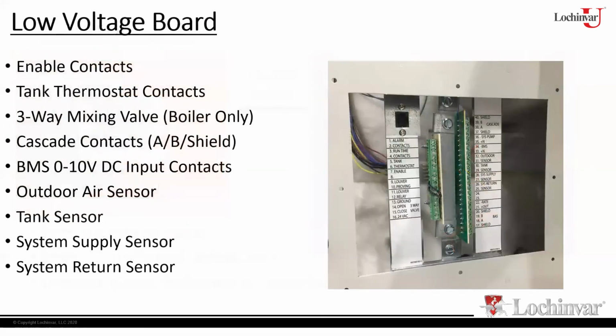Now on the back side of the heater will be our interface for your external items. This is our low voltage terminal board. This is where we're tying in all the external stuff, all of our sensors, all of our remote safeties, things of that nature. Now, as the name suggests, it is low voltage, it's 24 volts. However, do me a favor, if you're working back here, if you're moving wires around, turn the power off to the heater. While 24 volts will just tingle when you grab it, it doesn't hurt.